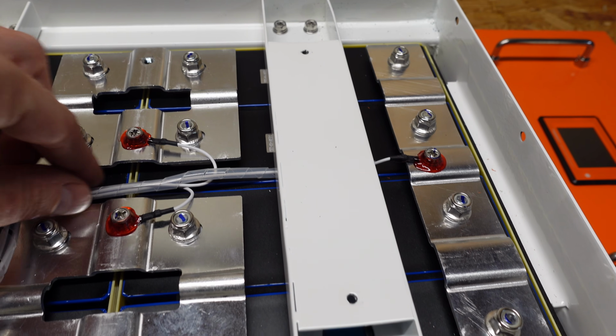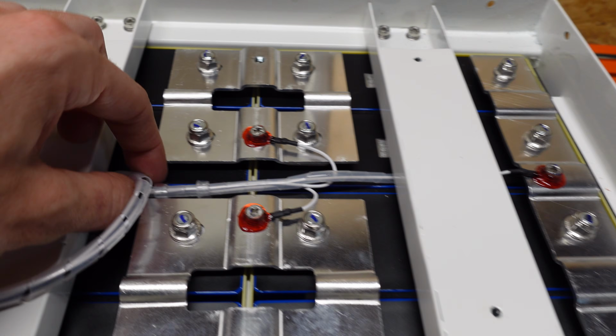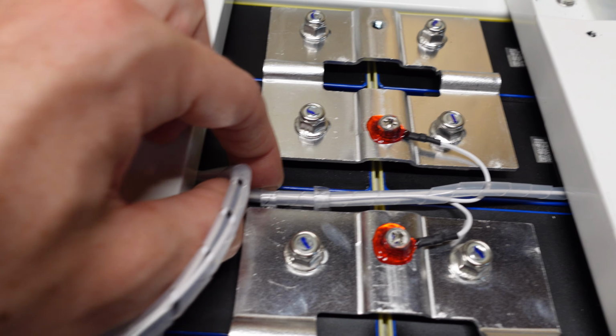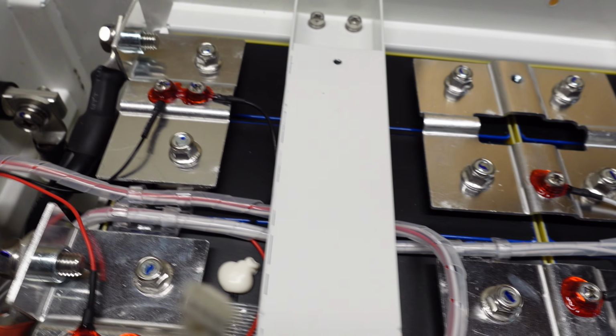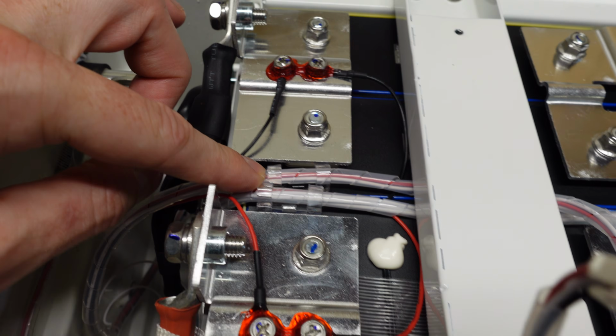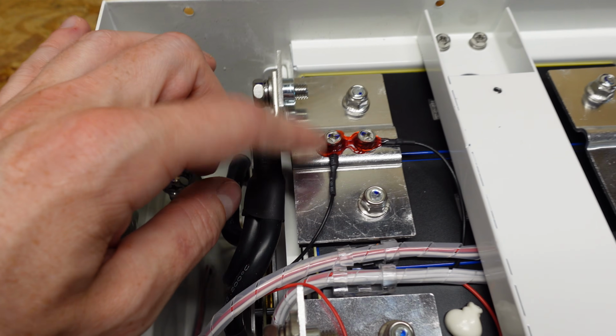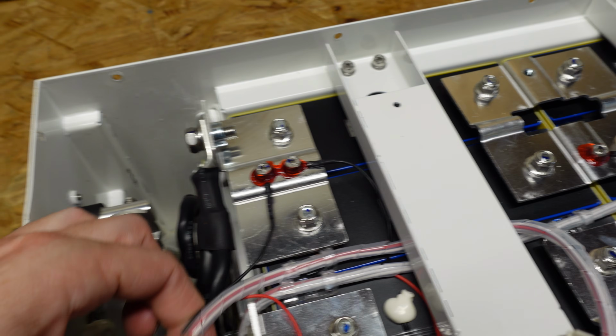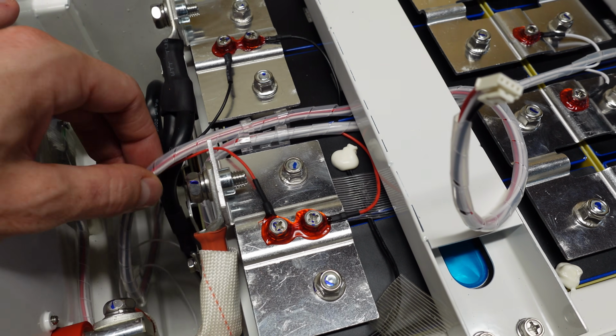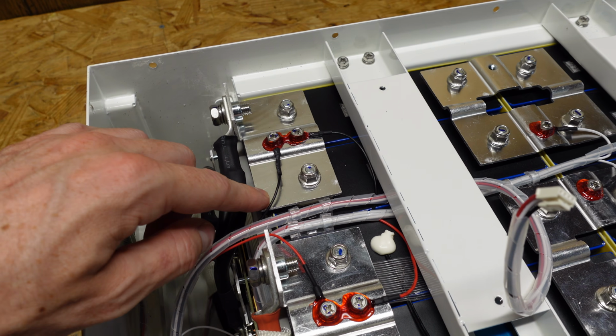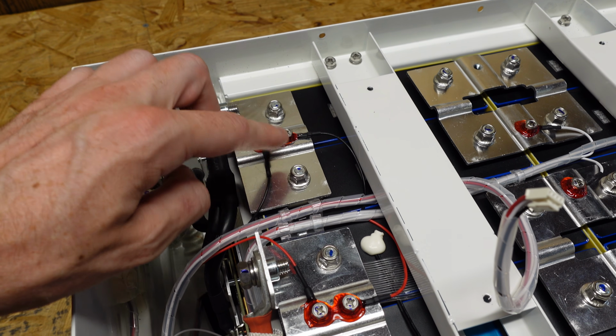The balance leads are all nicely routed down the center of the battery. They're held in place, look at that, it's actually held in place. Straight down to the front, it's held in place here again. We have 2 black leads on this one - what is up with the 2? There's 2 red leads here too. One of those must be power for the BMS, and the other lead is probably going to be the voltage sense leads.